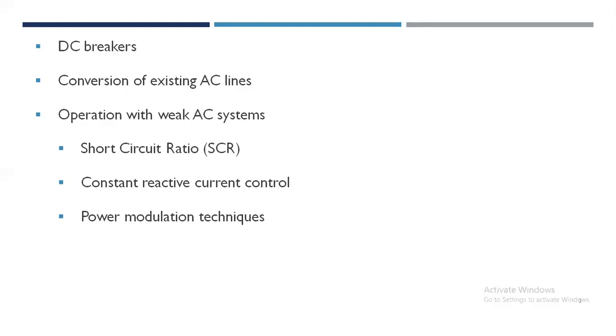Next is operation with weak AC systems. The strength of AC systems connected to the terminals of a DC link is measured in terms of the short circuit ratio, that is SCR, which is nothing but the ratio of short circuit level at the converter bus to the rated DC power. If SCR is less than 3, then the AC system is said to be weak. The conventional constant extinction angle control may not be satisfactory with a weak AC system. The recovery of inverters following the clearing of a fault in the connected AC system can also be problematic.